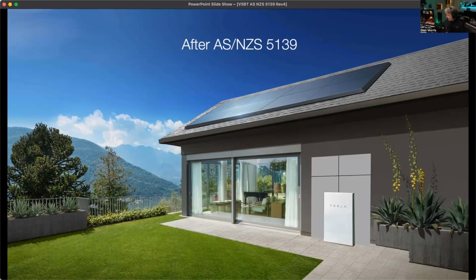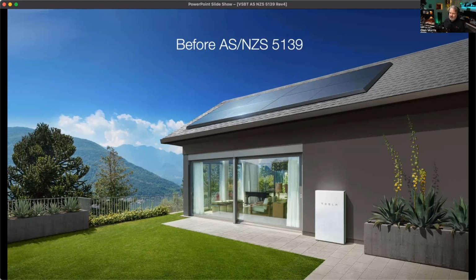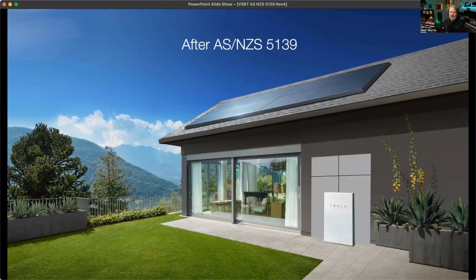So if I go back a slide, you'll see I had to move the pot plants too, because I had to shuffle the battery a bit further over to the right. I moved the pot plants with Photoshop and put up a fire barrier behind it. And of course, I've got to put all the signage, the warning signs, and it changes the whole look of it. It doesn't make customers very happy to have all these skull and crossbones signs everywhere, but it depends on whether the manufacturer lists things in their safety data sheets as dangers like toxic fume hazards and hazardous chemicals.